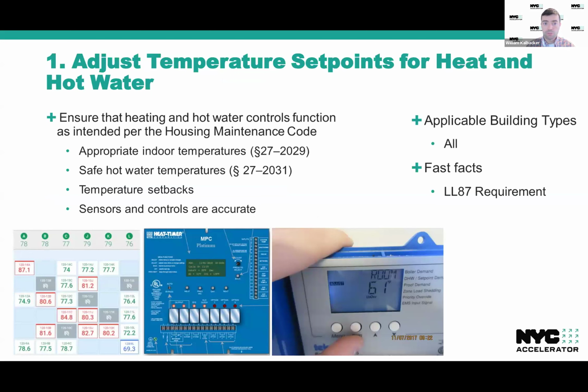So to get started, the first measure is to make sure that there are appropriate adjustments to temperature set points for both heating and hot water. Very generally, you want to make sure that the spaces that a heating system is serving are at the right temperature, but not too hot because you don't want to overheat. There are requirements in the housing maintenance code about what space temperature ranges are appropriate, and you want to make sure that you are heating your spaces to within those ranges, but not too much. You also just want to make sure that you are implementing setbacks where appropriate to save energy, and that the sensors and controllers are all communicating properly and are calibrated accurately. So this measure is going to apply to all building types, regardless of what type of heating system you have, and it does overlap with a Local Law 87 requirement, which I'll get to right now.